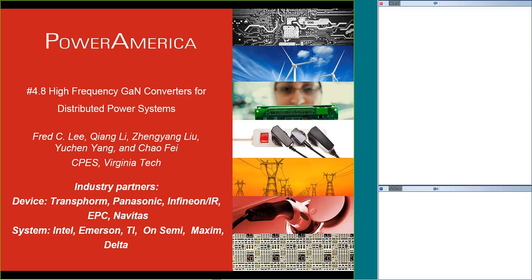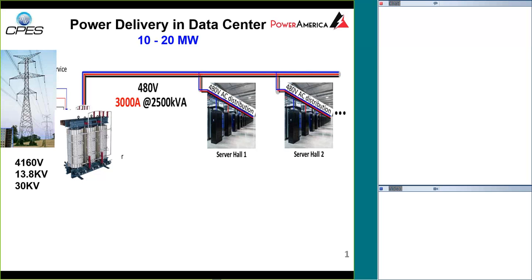The second topic is about using GAN devices for data center related applications. This page shows a data center. The larger data center is up to about 20 megawatts. For data centers, you start to draw power from medium voltage — smaller data centers will be 4160 volts, larger ones will be 13.8 kilovolts, and even larger ones would draw power from 30 kilovolt utility lines. You then go through a transformer and drop down to 480 volts three phase, with as much as 3000 ampere current through the cable, distributing power to various data halls.